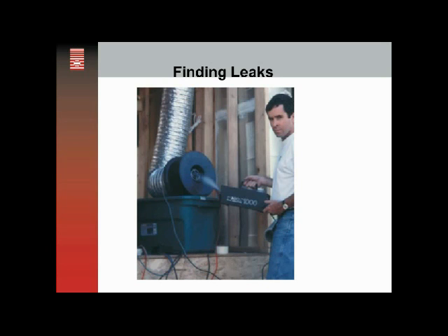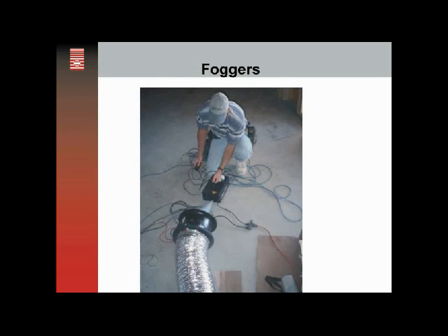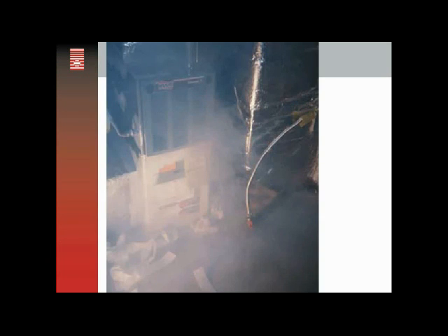Here's a shot of one of the best performance contractors in the country, Mike Uniac out of Arizona, pulling out a trusty theatrical fogger. Mike was a classic article where Mike was pressure testing installs on mechanical systems, again injecting theatrical smoke into the system, and you can see here's an install where the smoke is pouring out right at the air handler cabinet, or a connection between one of either the return or the supply plenum.